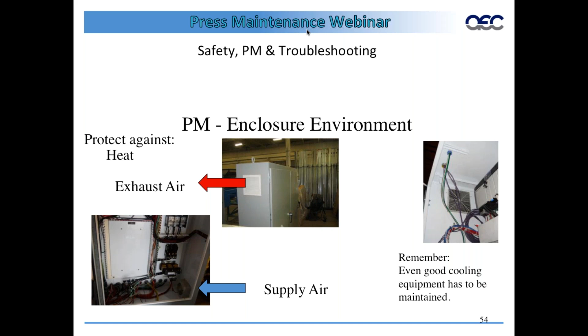You don't want it short circuiting and going out the same side, then you don't get any cooling effect. You pull heat out of the panel, but you don't cool the components. So when you go back, look for panels that are always running with the doors open, because there's an issue with heating. The quickest solution to that is to open the panel, and then you expose it to unsafe conditions. The proper way is to go back and find out why the cooling is not working, and if it doesn't have cooling, find a way to get the proper cooling.